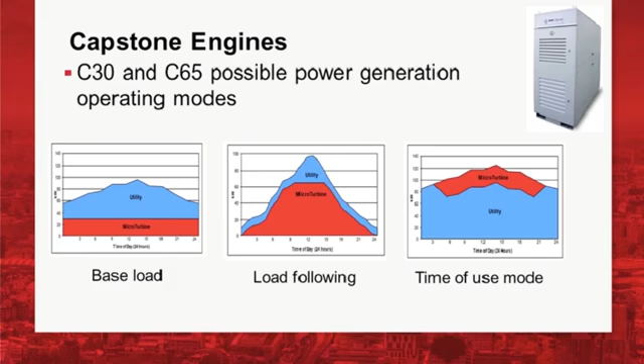The C30 and C65 have three possible generation operation modes. To the left, you can see they can be used as base load, operating at constant power output, which maximizes the overall efficiency of the system since it operates at its maximum efficiency point. They can also be used as load following, similar to large gas turbines used in the grid, or as time-of-use, switched on and operated as needed then switched off when there is no need, as utility power is available from other sources, as shown on the right-hand side.